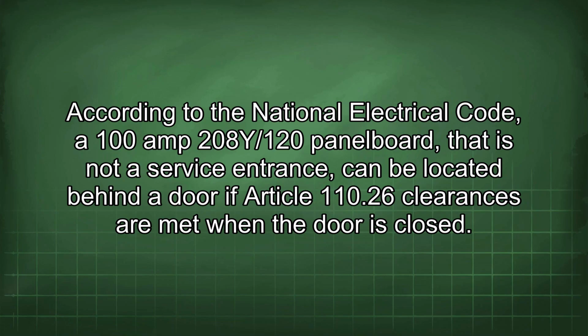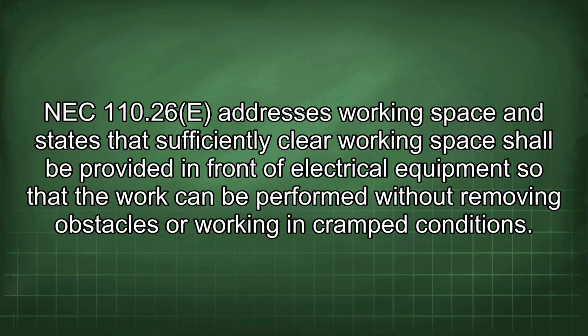According to the National Electrical Code, a 100 amp 208Y/120 panelboard that is not a service entrance can be located behind a door if Article 110.26 clearances are met when the door is closed. NEC 110.26e addresses working space and states that sufficiently clear working space shall be provided in front of electrical equipment so that the work can be performed without removing obstacles or working in cramped conditions.